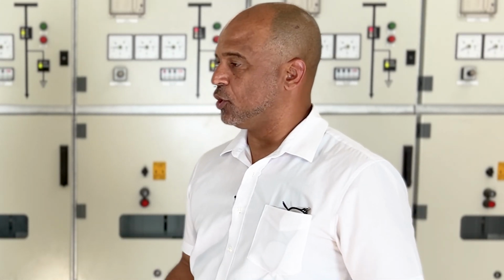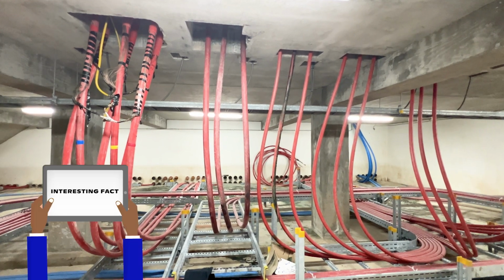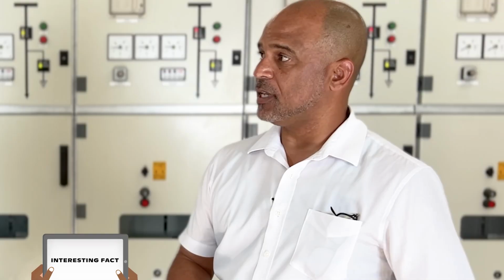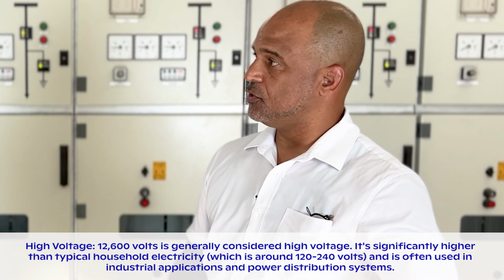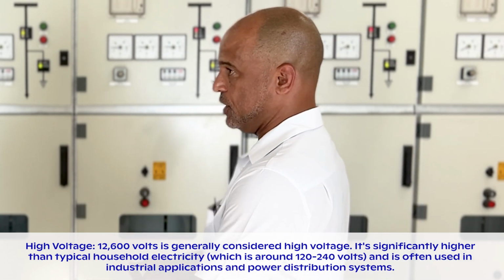So what you saw downstairs, the center cables coming in, the bigger, thicker cables, what we call the 240 cables - those are 240 aluminum single core cables that bring the 12,600 volts to this substation.